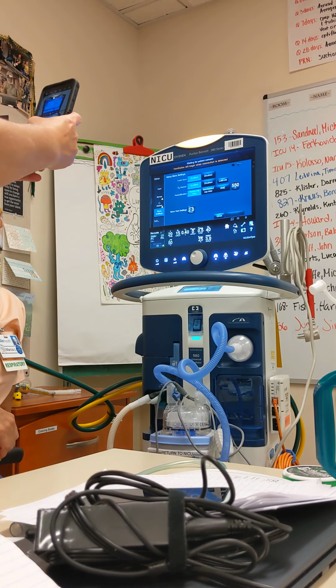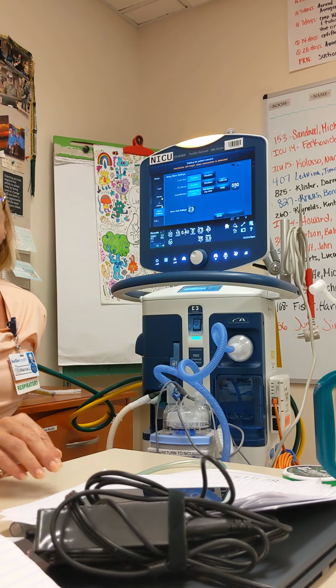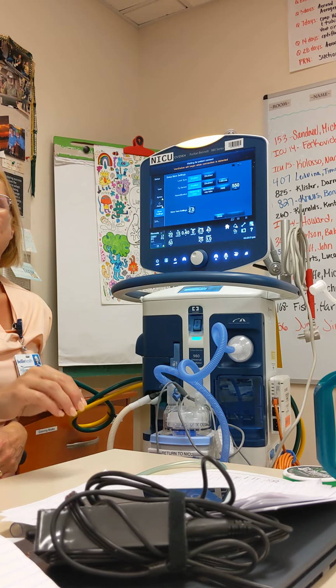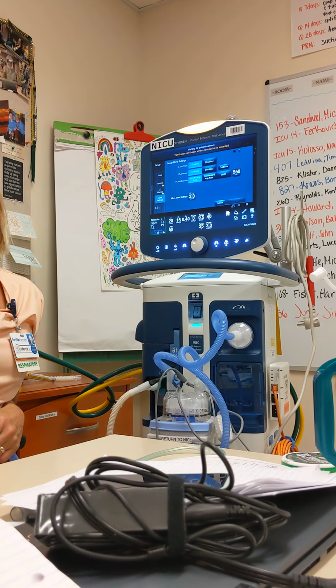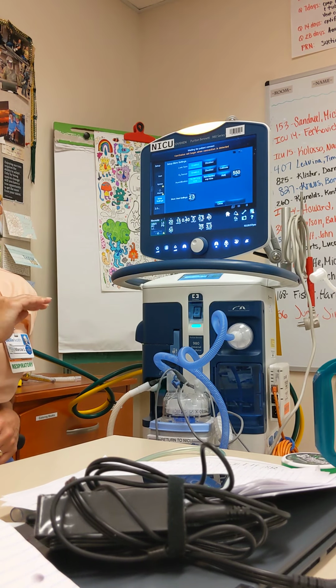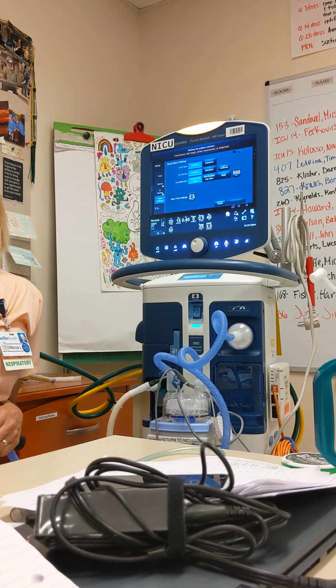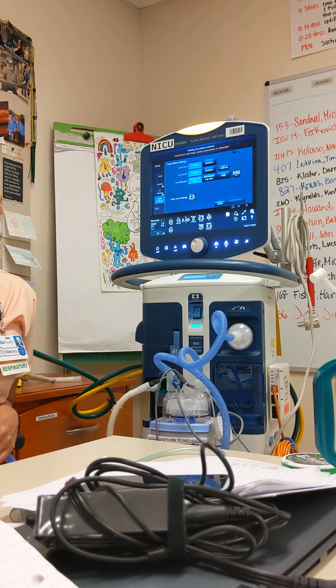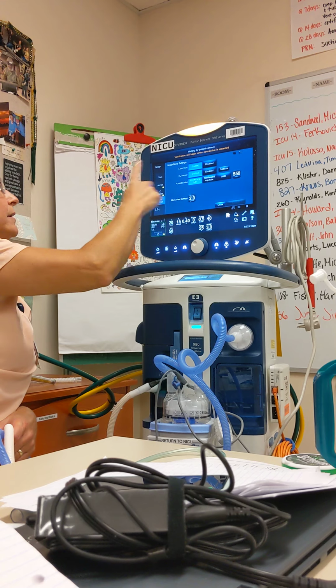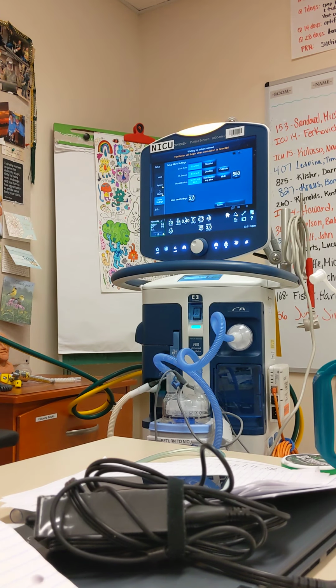The only other thing with the SST that is different when you're going through it is, there is one point where it says something about the proximal flow sensor. We're not using a proximal flow sensor in non-invasive, so it'll say to not use it, hit cancel. Got it. How did you switch it to non-invasive? I didn't yet. It probably is, but it's in a different setting. I have to go through a few different things now.